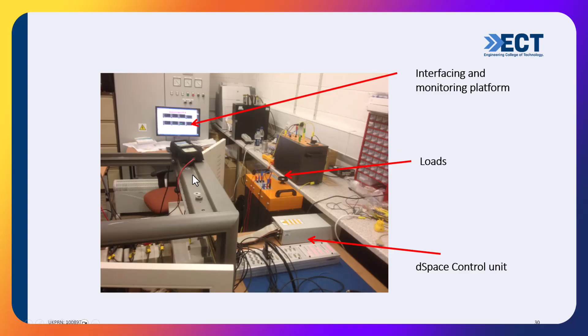...or in grid-connected mode. So if I go back to the first graph, here for example, all these units are already running. They don't need to run just because there is no grid. If you have a diesel generator that's not running at all, and it only runs in case the grid is absent, you need an ATS there. But you don't need an ATS in a normal microgrid running on inverters only.